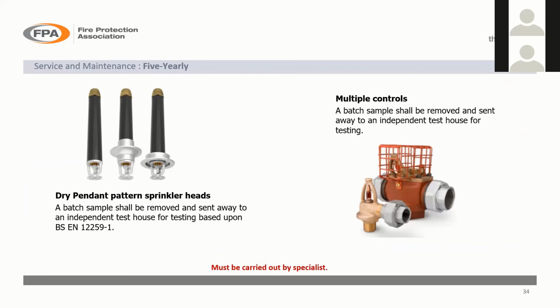So they need to be sent away, but just be aware that some manufacturers might require more frequent testing. So depending on what's been installed in your premises, that might be every 3 years, might be every 2 years. You need to check and look at what your manufacturers actually say.